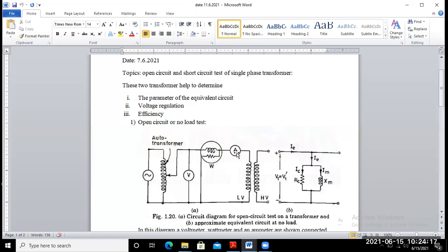With the help of the kVA rating, if voltage ratings are provided to you, first calculate the rated current of the transformer. Corresponding to that 2 to 12% of the rated voltage, you are able to get the rated current. So during this rated current, what is obtained from the wattmeter? The total power, that means ohmic losses plus core losses. Is it not? But the core losses in short circuit are very small.